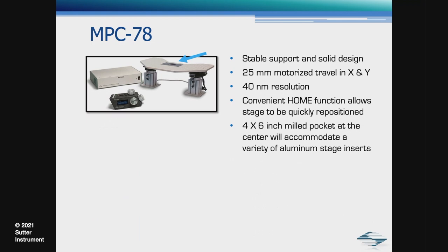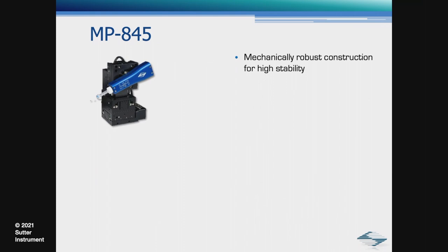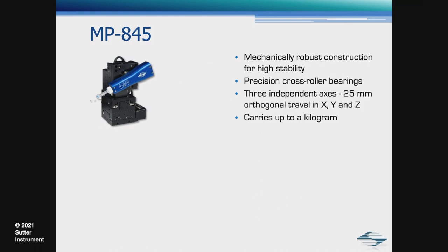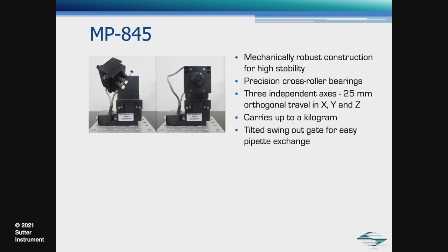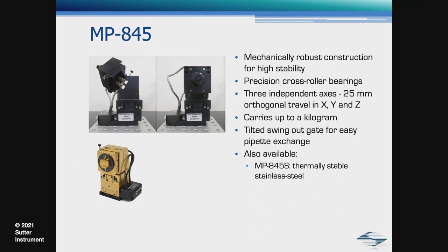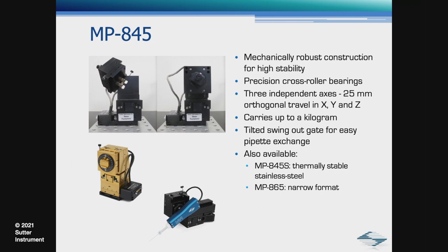In this setup, we used an MP845 manipulator, which is one of our newest manipulators. This manipulator is mechanically robust for high stability, uses precision cross-roller bearings, has three independent axes with 25-millimeter travel, can carry up to a kilogram, has a tilted swing-out gate for easy pipette exchange. Also available in the MP800 family is the MP845S, a stainless steel version which is extremely thermally stable, and a narrow format MP865.